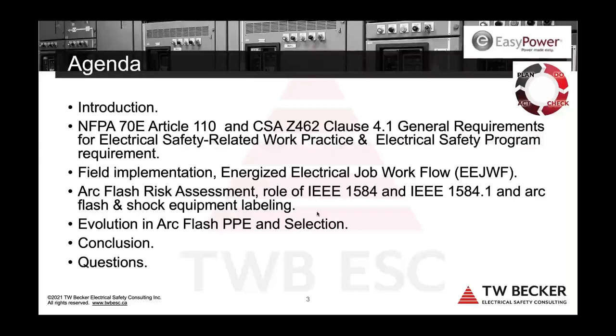So field implementation is where we need to take all of this: the arc flash hazard incident analysis calculations and the labels that are ultimately out there on the electrical equipment for the qualified person to be successful. So how do we take 70E and Z462 and their core requirements and get it out there into the field?